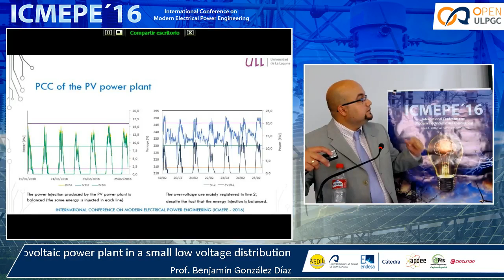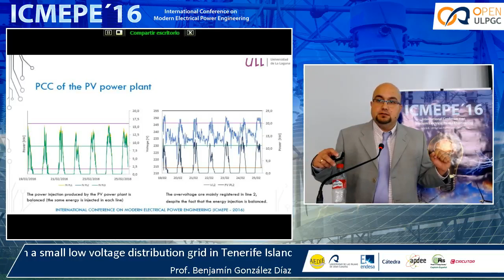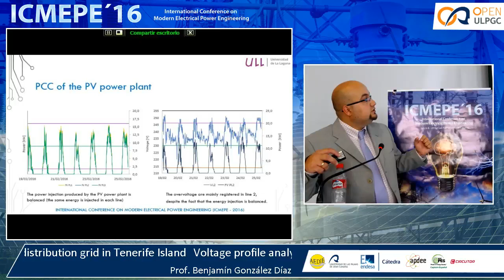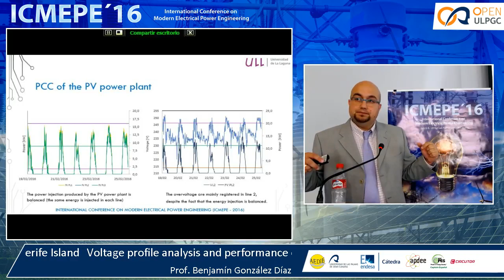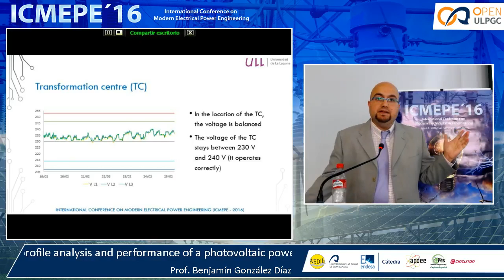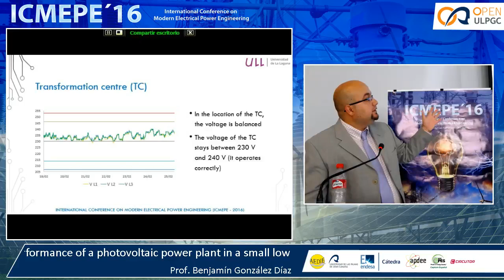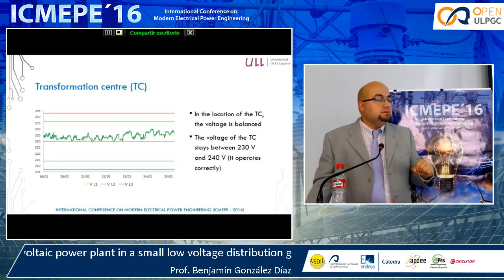But if we see the production of line 2 and the voltage of line 2, it matched perfectly. So in this line, the PV production is producing overvoltage of the line. We had a look at the transformation centre, and there is not any problem. The 3 phases were perfectly working all the time. They were working within the proper limits. There was not any kind of problem.